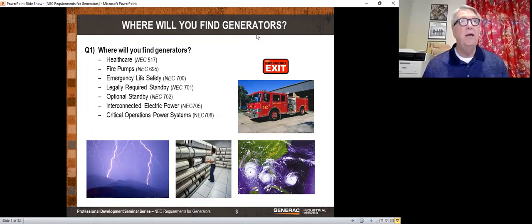So let me mention that when you come to me and you say, hey, I want an emergency generator, I just think, yeah, you want a standby generator. But if we're going to be more specific about that, and we actually have to when we're laying things out and doing pricing, there is a difference between an emergency generator, a legally required generator, and an optional standby generator. And it's very important that you know which type of generator you have, because that will determine which generator you buy and which standards you have to meet. And we will get into that extensively in the next 45 minutes.